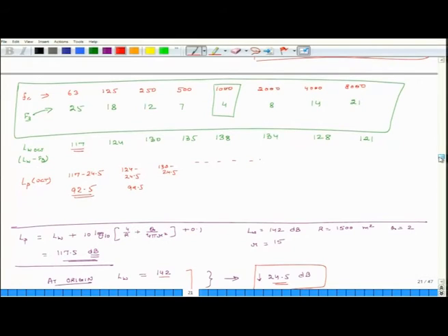So, what is happening in each octave band? In this octave band, we do not have 142 decibels, we have just 117 decibels of power level. So, what will be the pressure level? I have to just bring down the pressure level by 24.5 from here. And I do the same thing for all other frequency bands. So, in this way I can calculate LP octave.